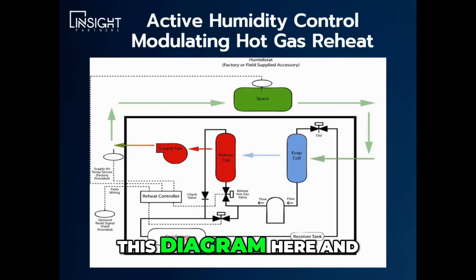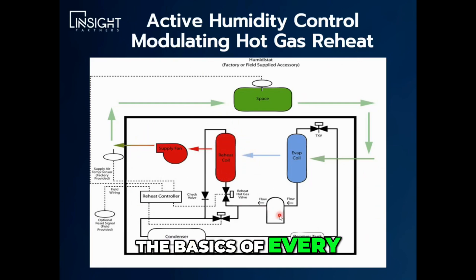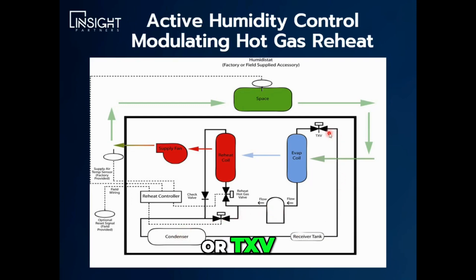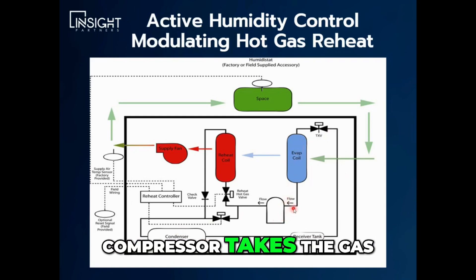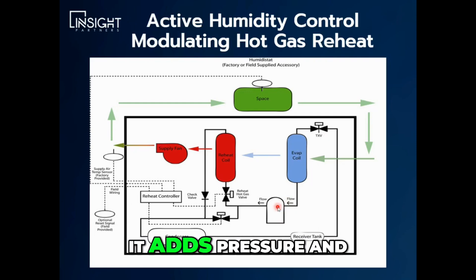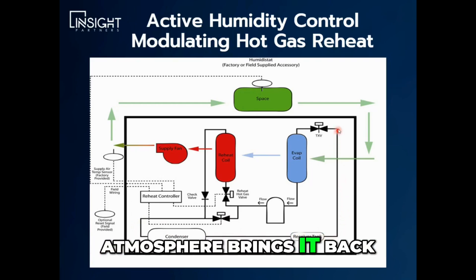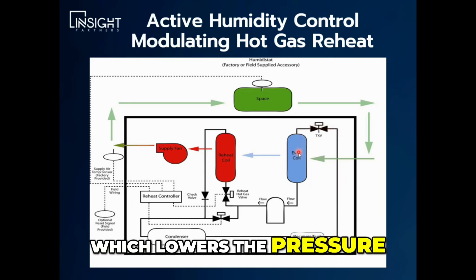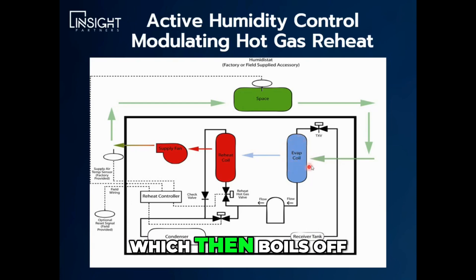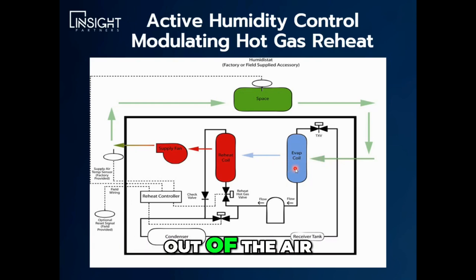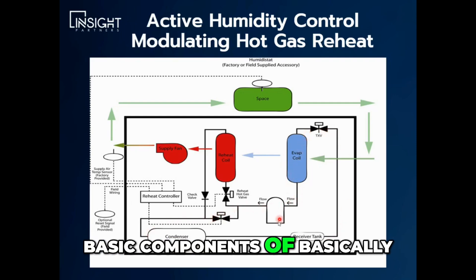So this is modulating hot gas reheat. If you take this diagram here and remove the reheat coil, what you have is the basics of every HVAC refrigeration system: a compressor, condenser, your thermal expansion device or TXV, and evaporator coil. What happens is your compressor takes the gas from the evaporator, adds pressure and temperature to the gas, sends it over to the condenser coil, which then rejects much of the heat to the relatively cool atmosphere, brings it back around to the thermal expansion device, which lowers the pressure, and sends this liquid to the evaporator coil, which then boils off from the heat from the air going across it. So that takes the heat out of the air, puts it in the refrigerant, turns it into a gas, sends it back to the compressor. So that's your four basic components of basically every refrigeration cycle.